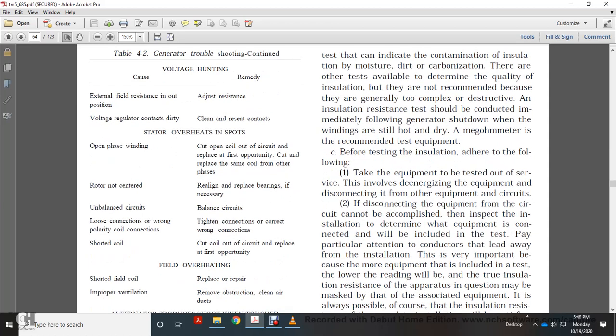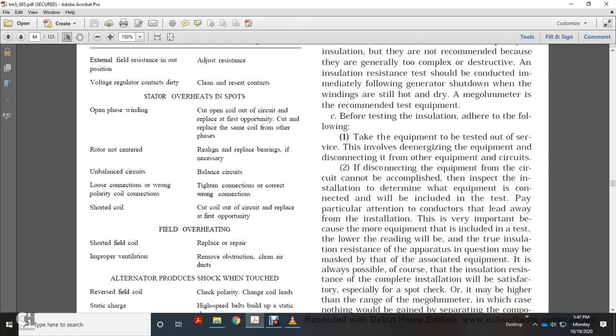Pay particular attention to conductors that lead away from the installation. This is very important because the more equipment is included in the test, the lower the reading will be, and it will not be the true insulation resistance of the apparatus in question may be masked by that of the associated equipment. It is always possible that the insulation resistance is satisfactory.